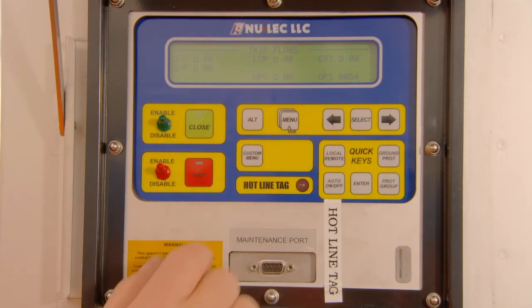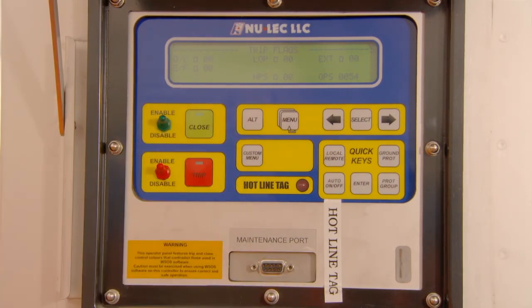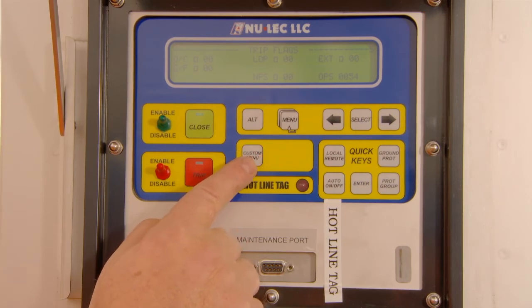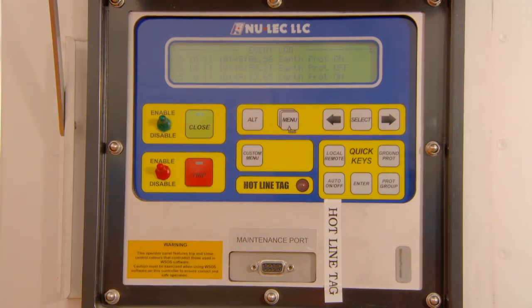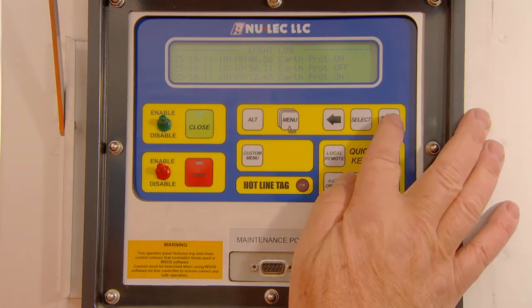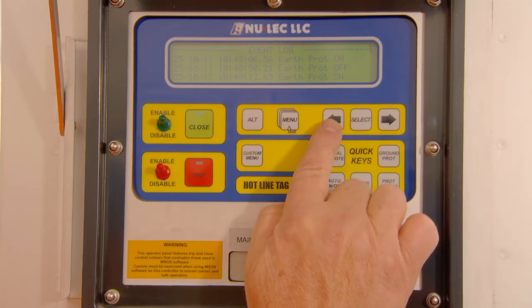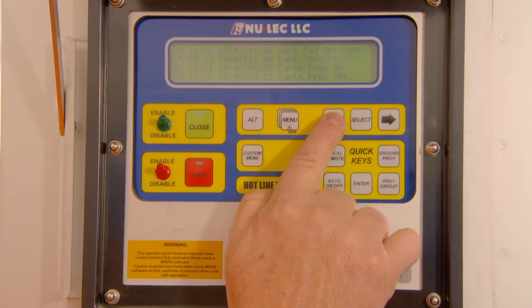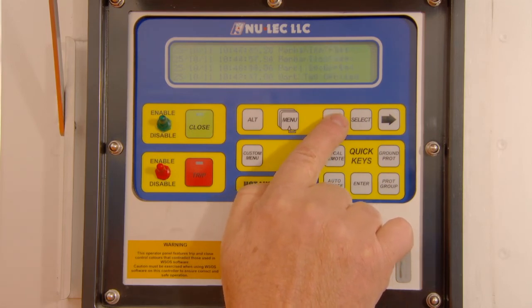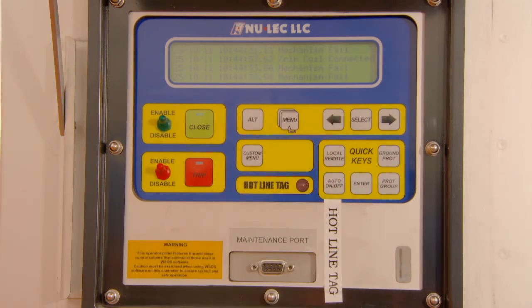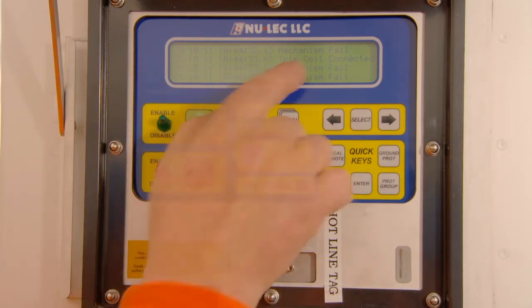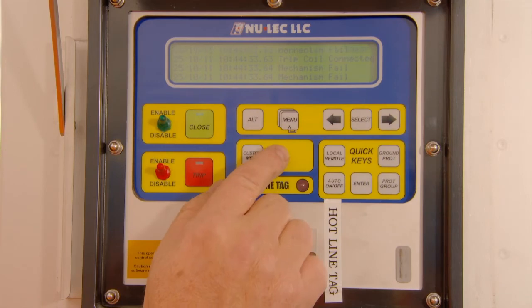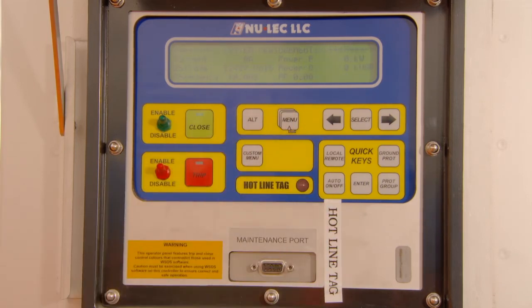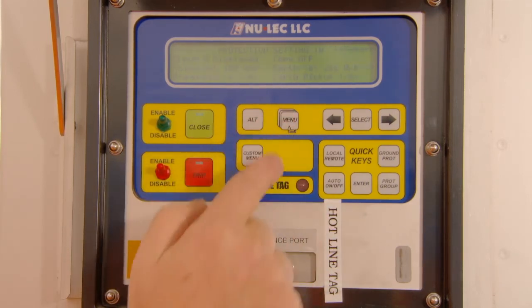The Custom Menu button has been programmed to provide information that you will require. Pressing the button will first take you to the Events log. You can scroll down through the log using the left arrow button, the latest event being at the top. The event log gives you the date and time, as well as the cause of the fault. To exit from the event log, press the Menu button a number of times until you reach the main menu.